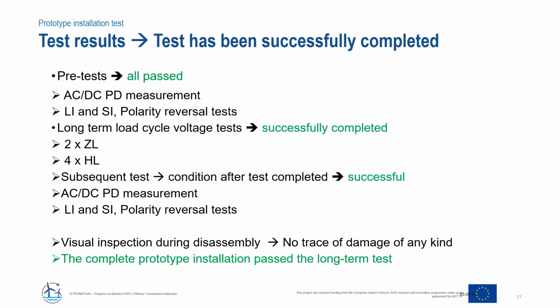And of course, subsequent tests to check the condition of the test object have been performed, which included AC, DC, partial discharge measurement, and lightning impulse of different polarities. And then of course visual inspection during disassembly, which showed no trace of any kind of damage, and this shows a complete successful demonstration of the HVDC GIS prototype installation.